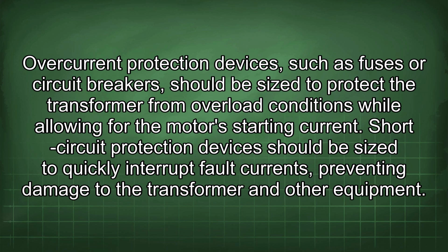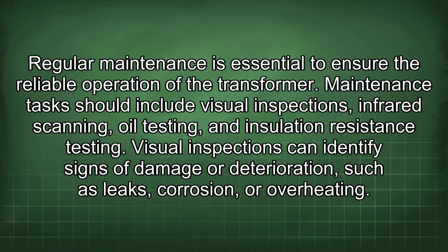Overcurrent protection devices such as fuses or circuit breakers should be sized to protect the transformer from overload conditions while allowing for the motor's starting current. Short circuit protection devices should be sized to quickly interrupt fault currents, preventing damage to the transformer and other equipment. Regular maintenance is essential to ensure the reliable operation of the transformer. Maintenance tasks should include visual inspections, infrared scanning, oil testing, and insulation resistance testing.